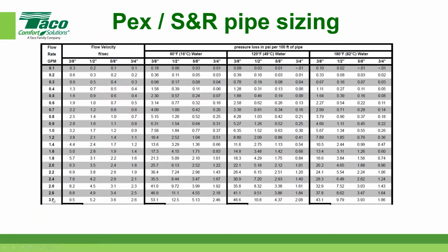Now notice, I had 3 gallons a minute. I'm just showing somebody's PEX pressure drop calculation. So I'm going to use 3. I'm going to come over here to 3/4 inch. And if I ran 3 gallons a minute through, there's my 3 gallons a minute, through a piece of 3/4 inch PEX. And remember, PEX, because it's a flexible piping system, is more affected by the temperature of the fluid running through it. So it actually relaxes a little bit the hotter that it gets, and the pressure drop is slightly less. Okay. So just remember, there's a temperature contingency on flexible piping systems, and the manufacturer of the product will give that to you.